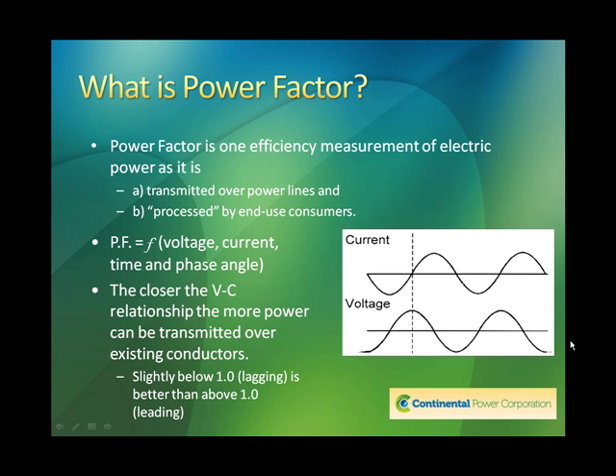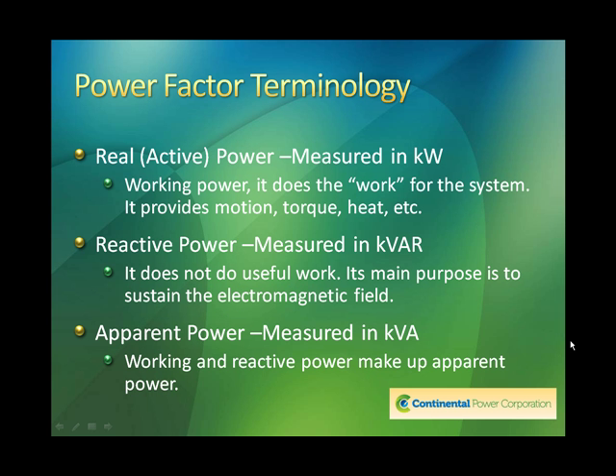Now, looking at that diagram, you see the voltage, the dotted line, is showing where the voltage begins, and you see it's peaked right at the dotted line and it starts to go down. You look at the current, well, the current doesn't peak until farther to the right or a short time later. The difference between the peaks, that measurement of time, is how we calculate power factor. And there are instruments that do it very well. As long as we can clamp around the conductors and get a current measurement and clip on to the voltage and the power line and the neutral, or if it's a three-phase system between power lines, we can get an accurate power factor measurement.